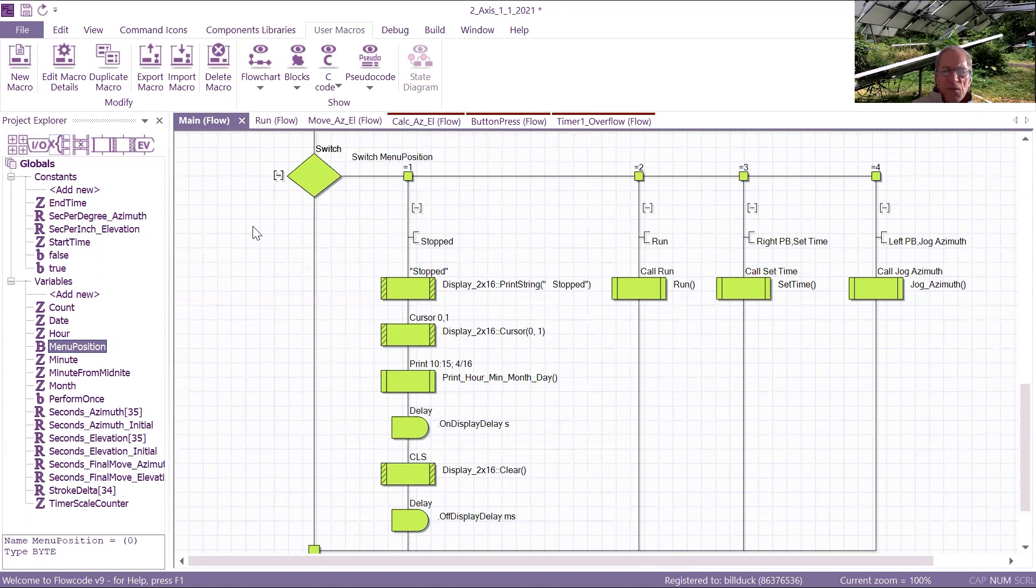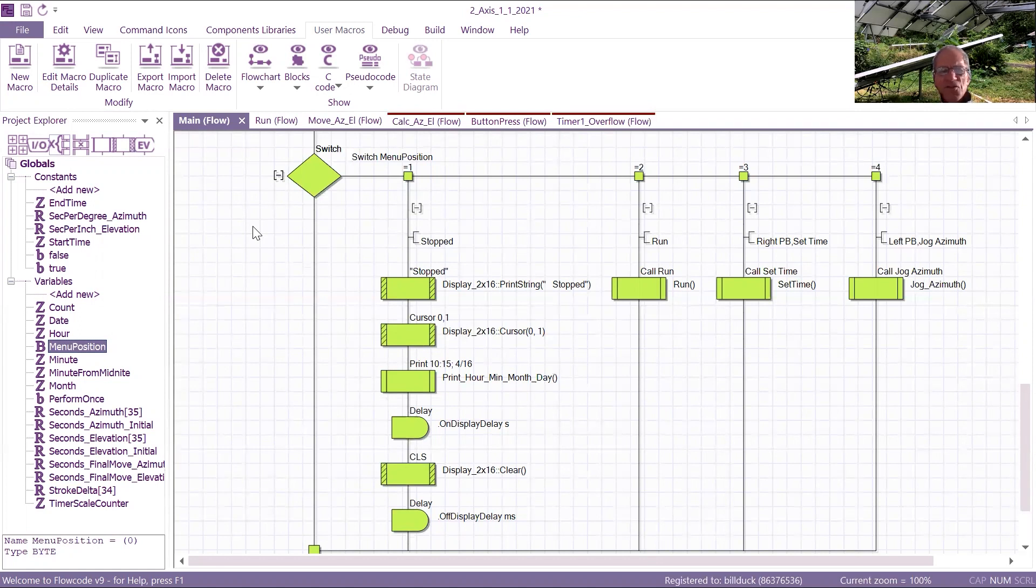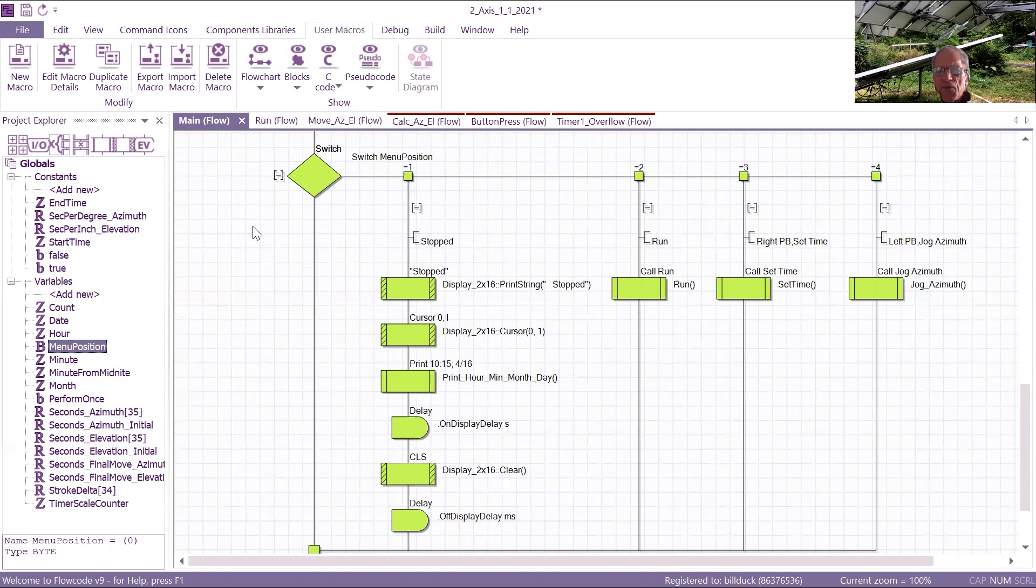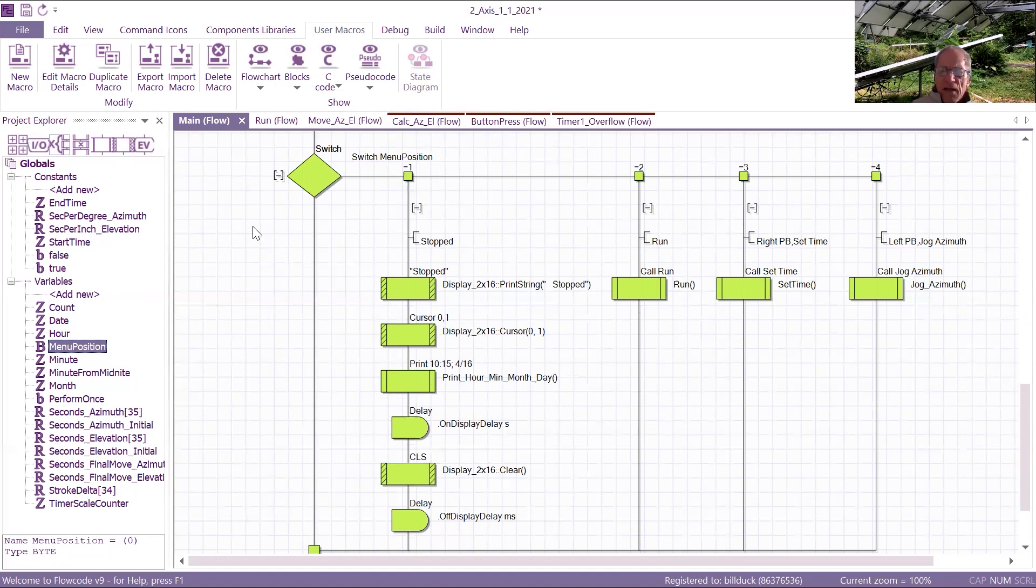For example, on the azimuth, if it were mid-stroke, I wouldn't know which way to go, but if I put the limit switch at the end of the azimuth movement, I can seek it and then move halfway back to, incidentally, I might say I store the array at horizontal, in a horizontal position at nighttime, merely because wind loading, we have hurricanes in Houston, and wind loading is an issue, or if there's an extreme weather event, I want it to be horizontal, and I can do that at nighttime. I suppose in the future, if I could have a wind speed sensor, and if the wind picked up, I could store the array horizontal also. More to come.